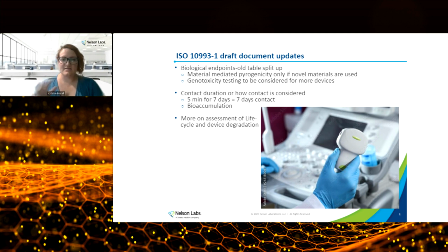One of the other points that feeds into this, and is more emphasized in the updated standard, is bioaccumulation. The exact definition isn't 100% clear just yet, but there is more discussion on considerations you'll need to make about this potential. You're going to need to look more at your materials, not just what's on your device, but what's used during the manufacturing or even the packaging. Are there things that could potentially bioaccumulate in the body, and how do you address that? So there's definitely a lot more expertise that's going to be needed to do these assessments.